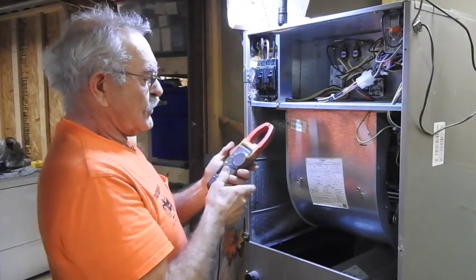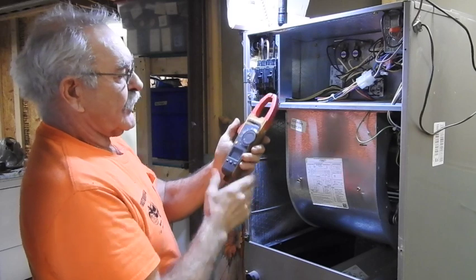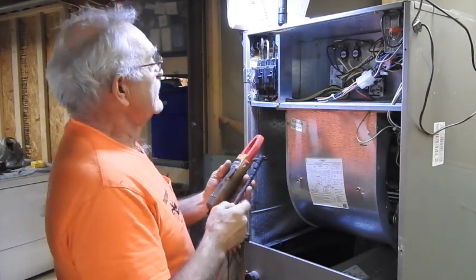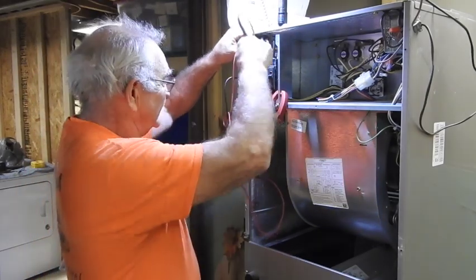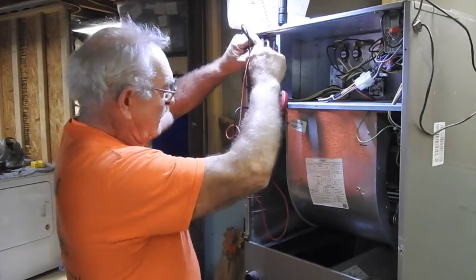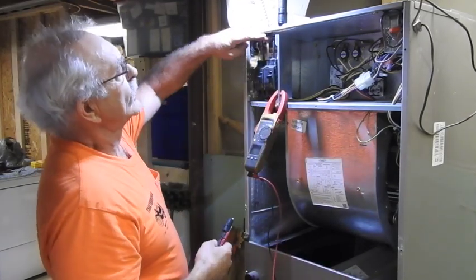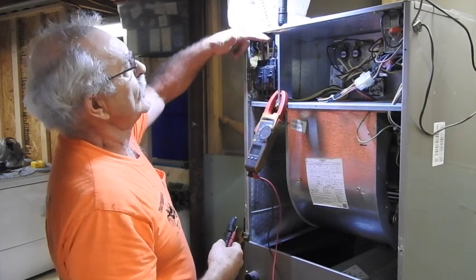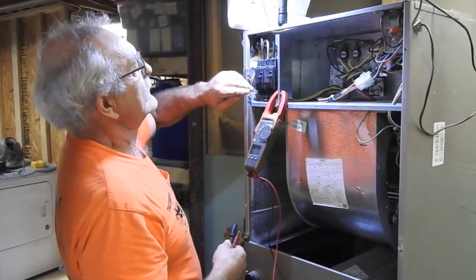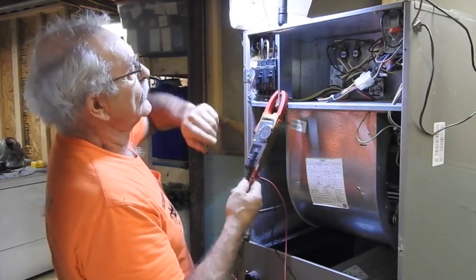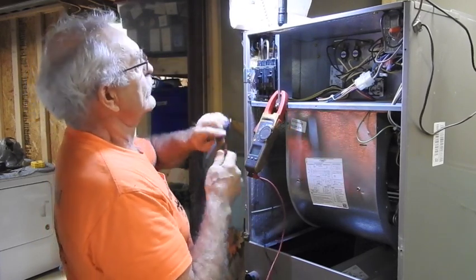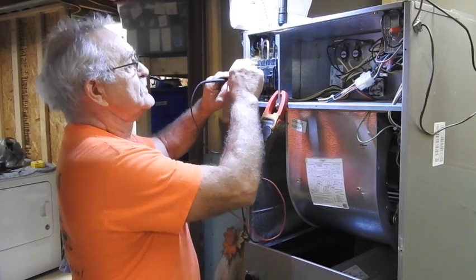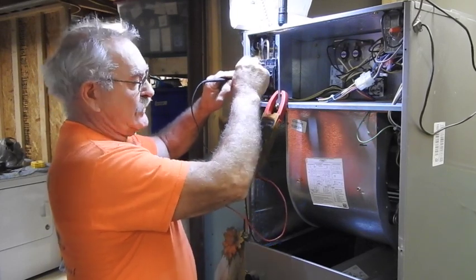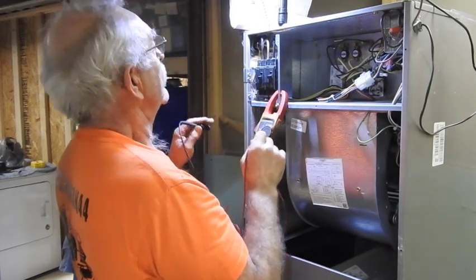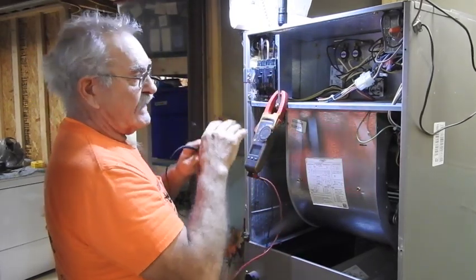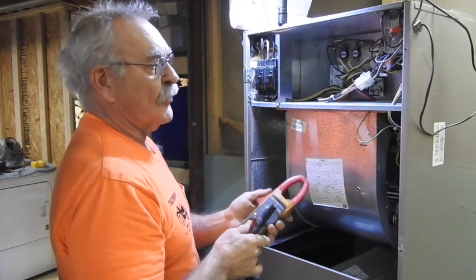Anyway, here's our breakers here. I told you I had them turned off. Get yourself on the proper scale, which is AC voltage. 0 volts, 0 volts. Now, the way this works, this is a dual circuit furnace. It's got two number 6 wires coming in, supplying these 60 amp breakers, and the black and white is going to be the 240 volts. If you want to, you can just for the heck of it check each one individually to ground, and you should get roughly 120 to ground. But verify above all else that everything is dead first and foremost before you stick your fingers in there.